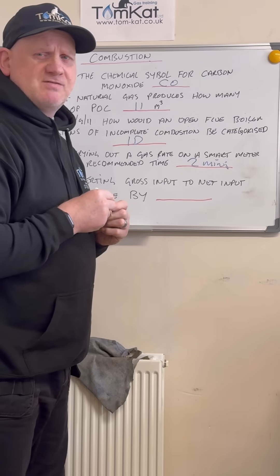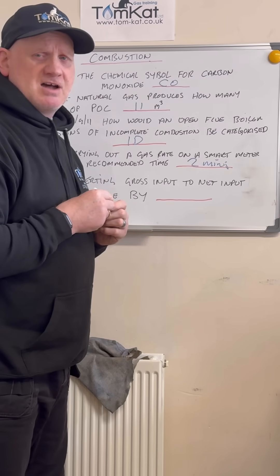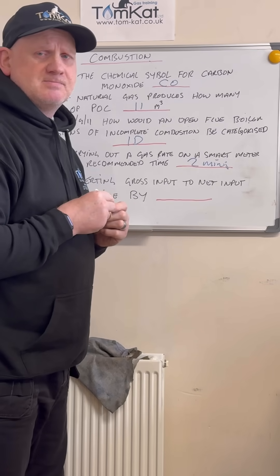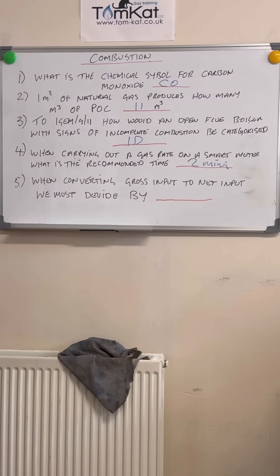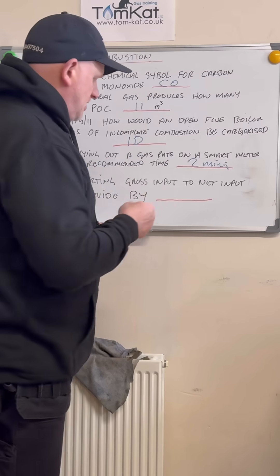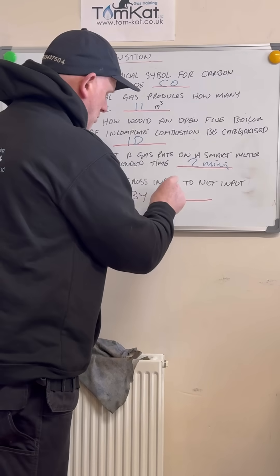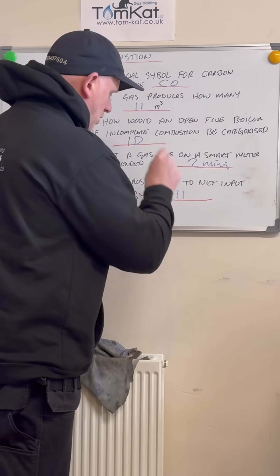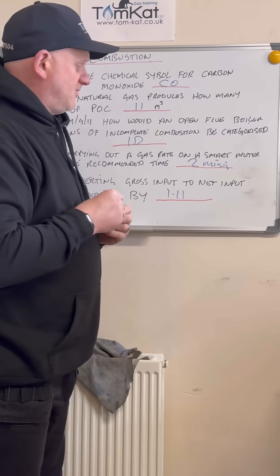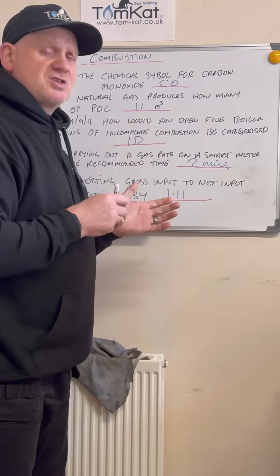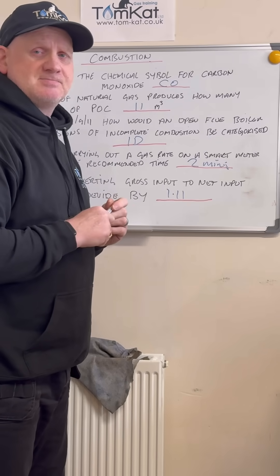Question five and halfway there. When converting gross input to net input, we must divide by — hopefully you said 1.11 — because that's how we convert gross to net for natural gas.